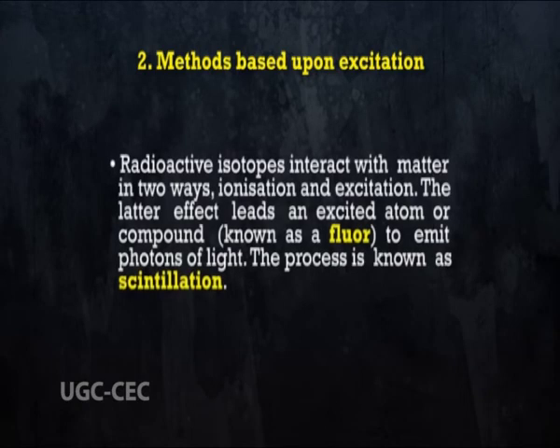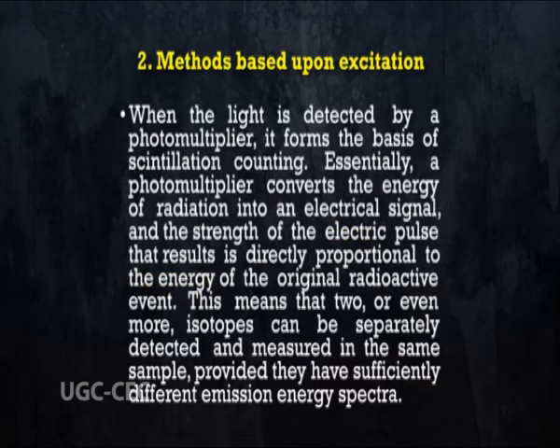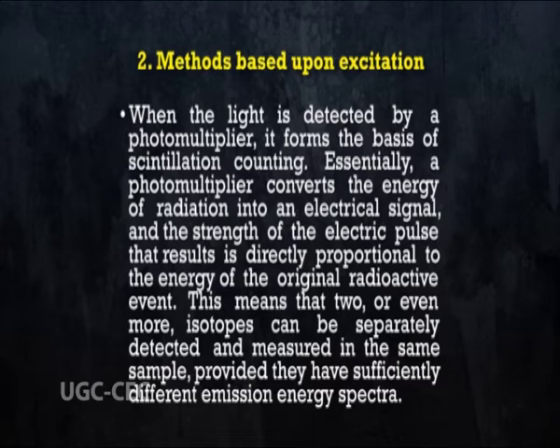The second method is based upon excitation. Radioactive isotopes interact with matter in two ways: ionization and excitation. The latter effect leads an excited atom or compound, known as the fluor, to emit photons of light. The process is known as scintillation. When the light is detected by a photomultiplier, it forms the basis of scintillation counting. A photomultiplier converts the energy of radiation into an electrical signal, and the strength of the electric pulse is directly proportional to the energy of the original radioactive event. This means that two or more isotopes can be separately detected and measured in the same sample, provided they have sufficiently different emission energy spectra.